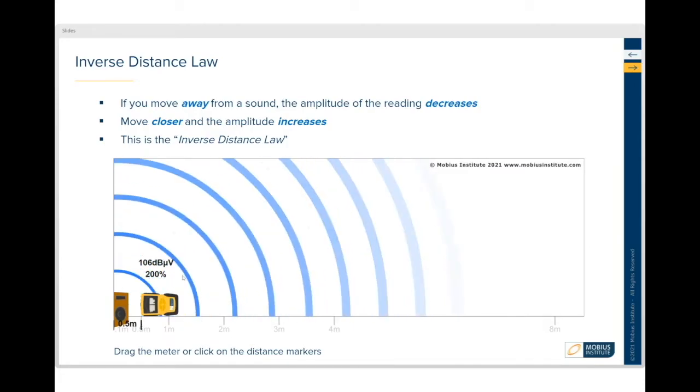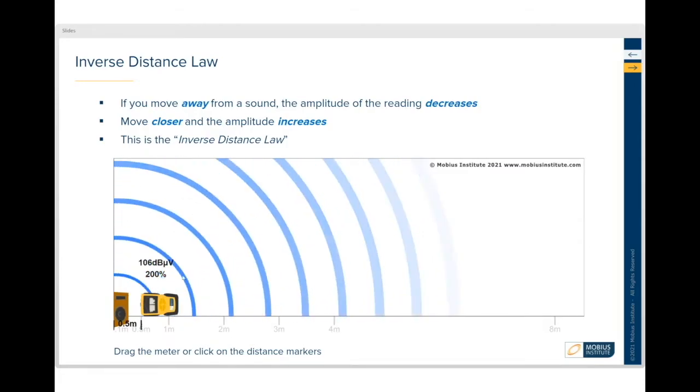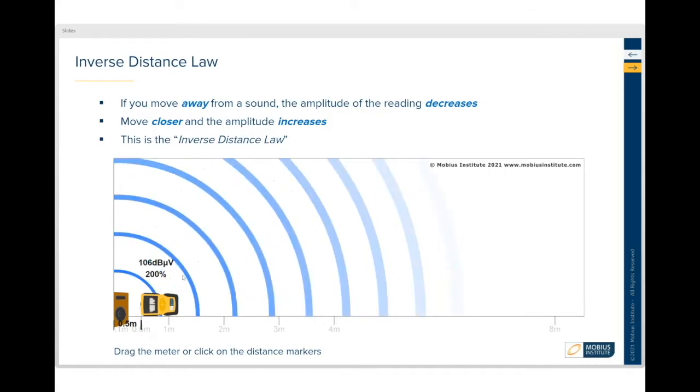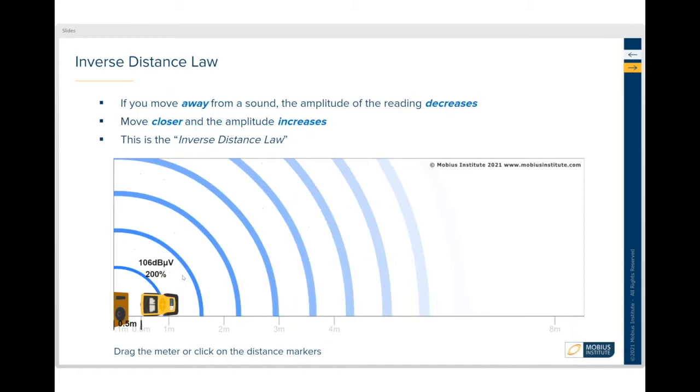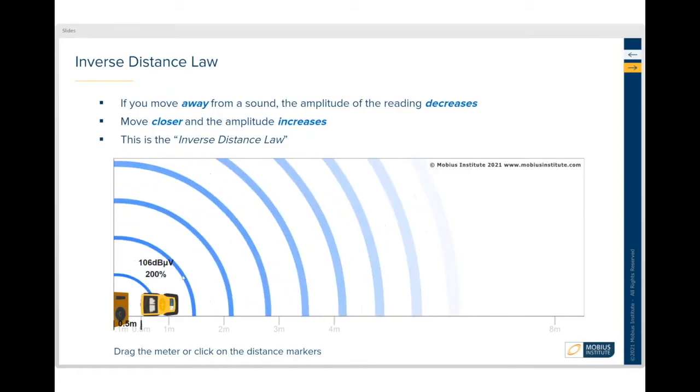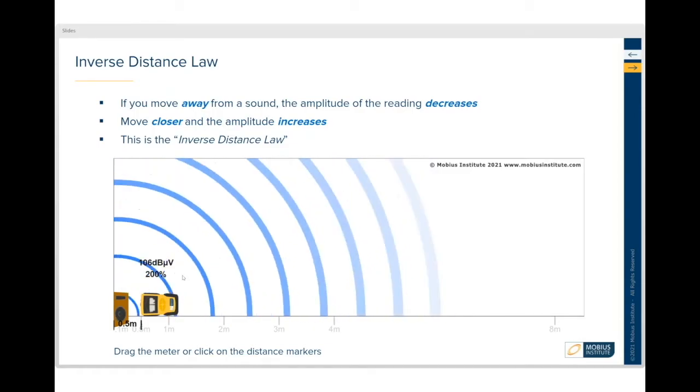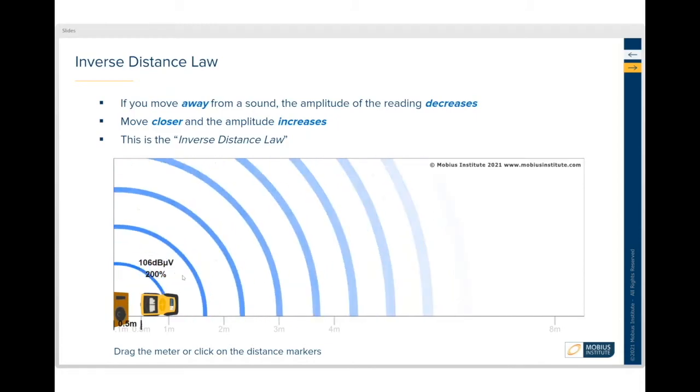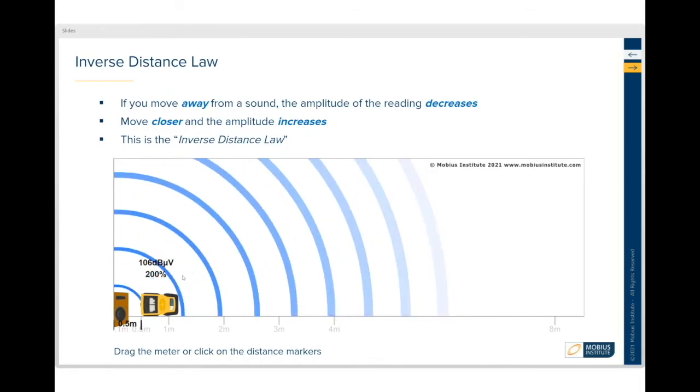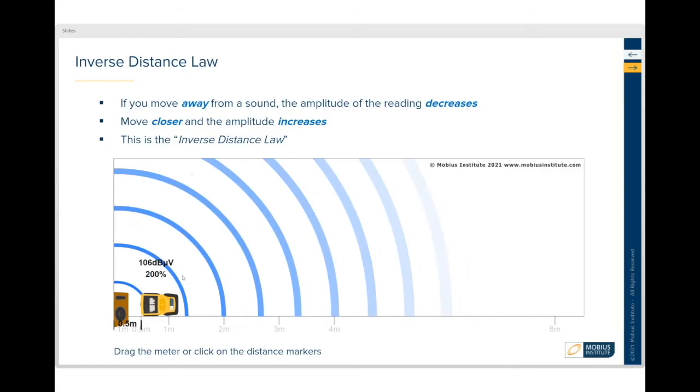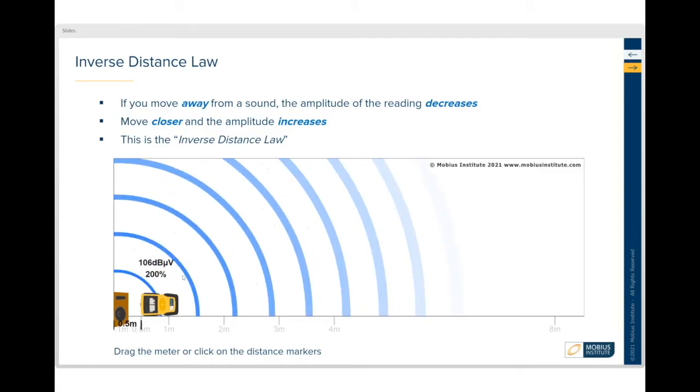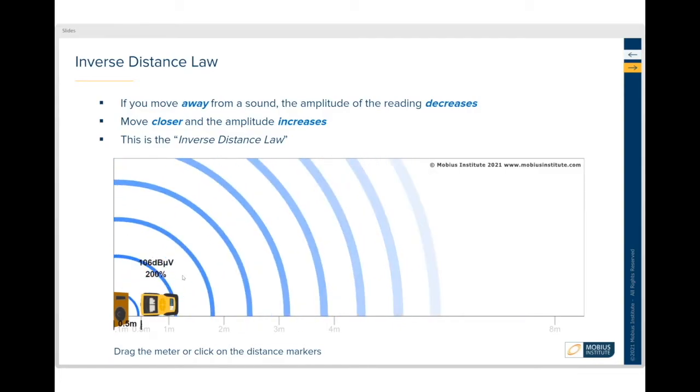It also means that we must be consistent in the way we take our measurements. If we stand at different distances at different times when taking airborne measurements, we will get different readings for the same piece of equipment. Repeatability is very important with ultrasound as it is with all testing techniques.